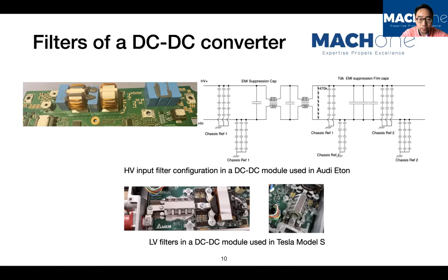Often manufacturers use cores, either ferrite or nanocrystalline, depending on the frequency range you want to filter out, and they put the cores along the bus bar lines. If you insert both bus bar lines into the cores, you form a common mode choke. If you just put V bus plus together with some capacitors after, you build an LC low pass filter stage, which I think is exactly the configuration shown in the Tesla module.